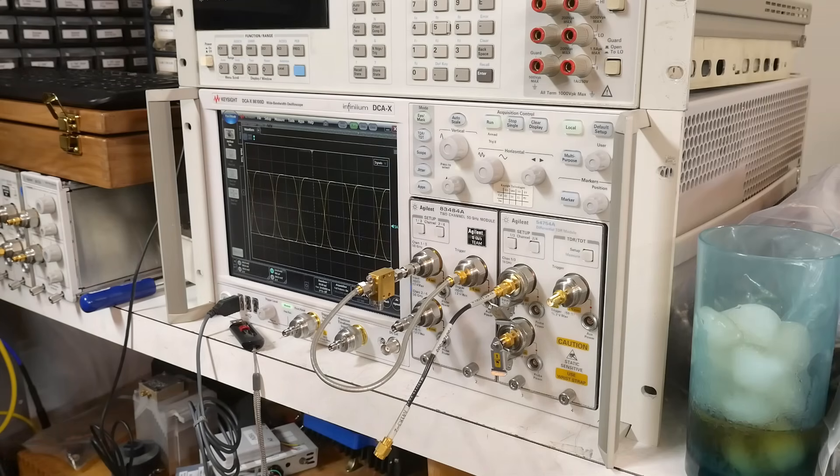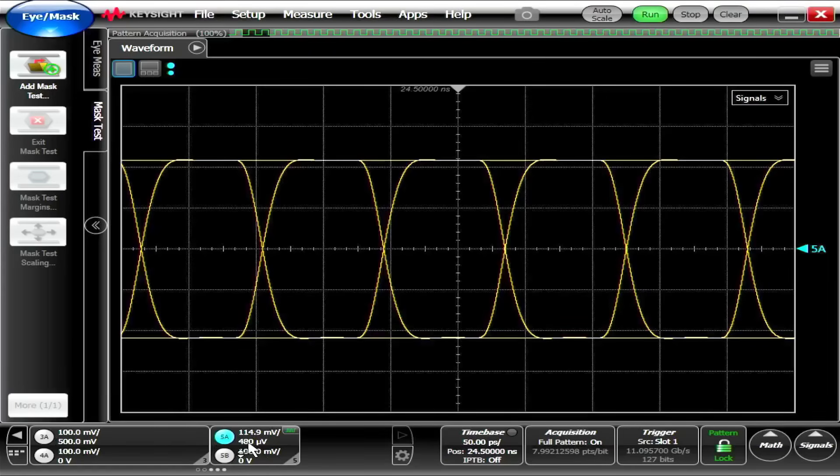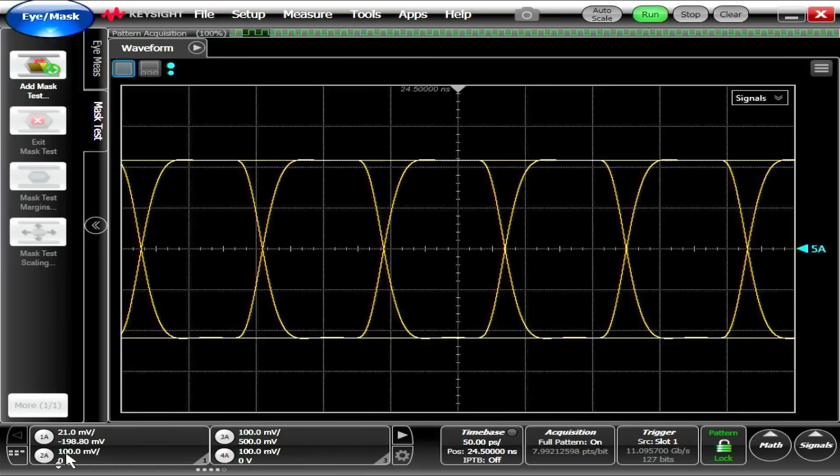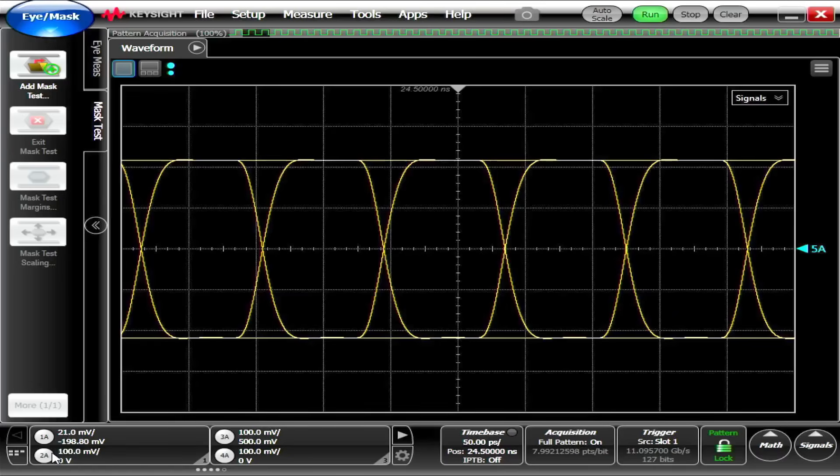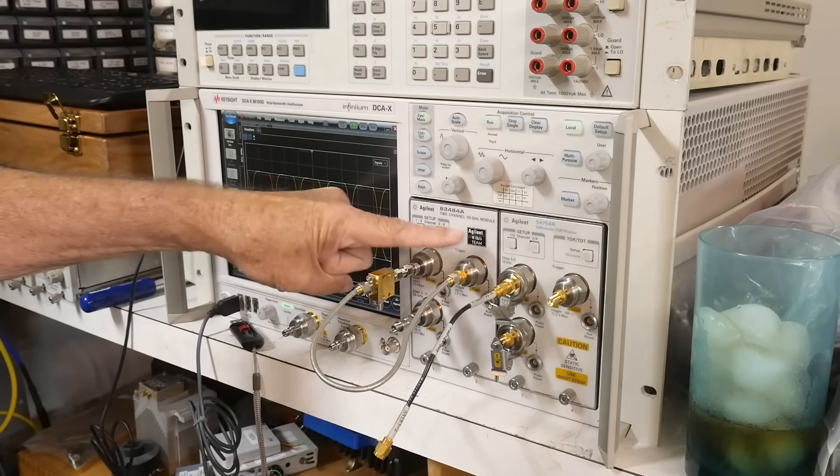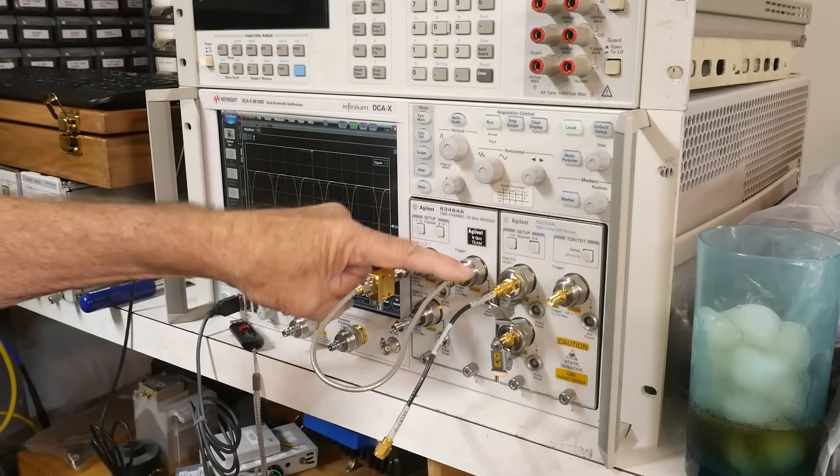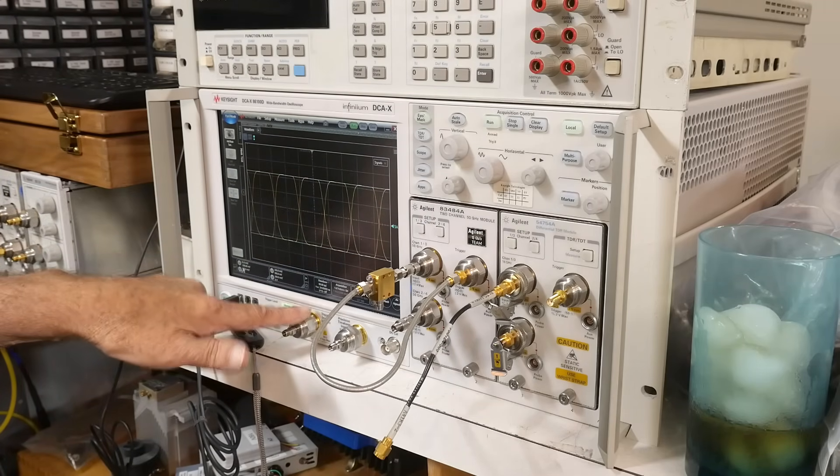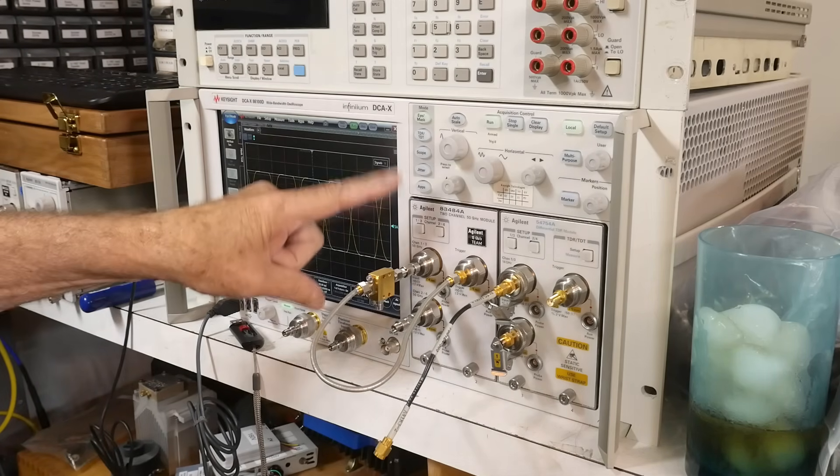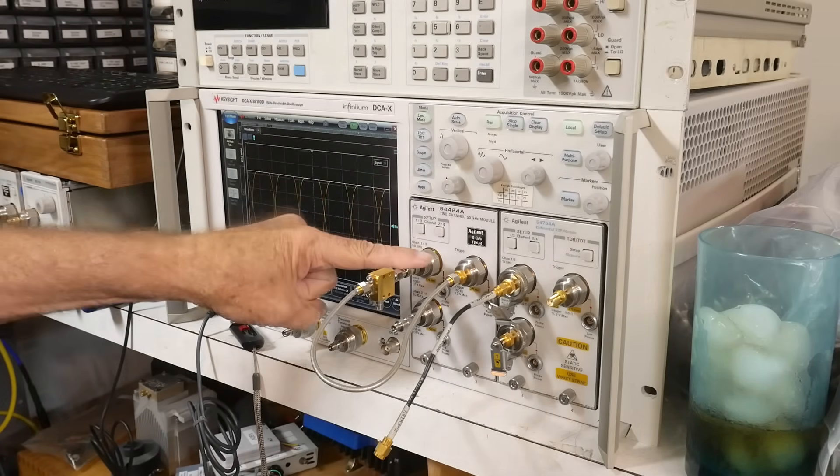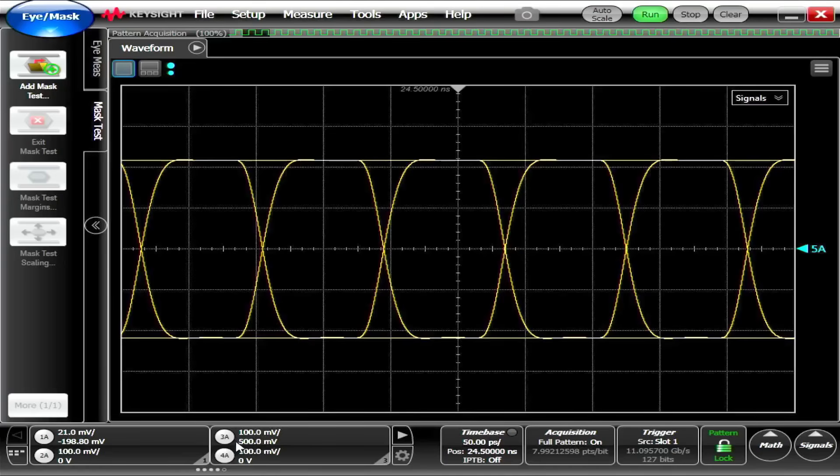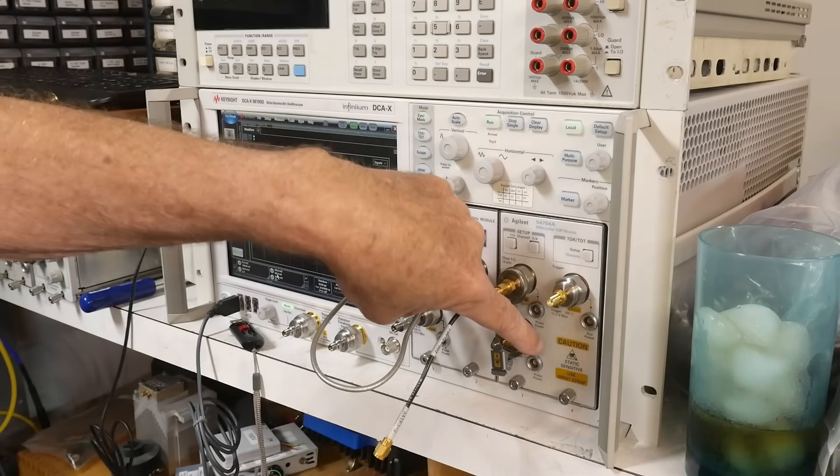So one of the things that you find is down at the bottom here, there's a little area where we can select what channels do we want to turn on. We have channels 1A and 2A. Those are here on this plug-in, so this is 1 and 2 right here. 1 and 2. This is the trigger input. The difference between trigger input here and trigger input down here is just a relay. There's nothing that happens inside this plug-in, it just goes straight through and goes into the machine. So channel 1, channel 2, and then over here at the bottom is channel 3A and 4A. That's these. This is channel 3A and this is 4A.